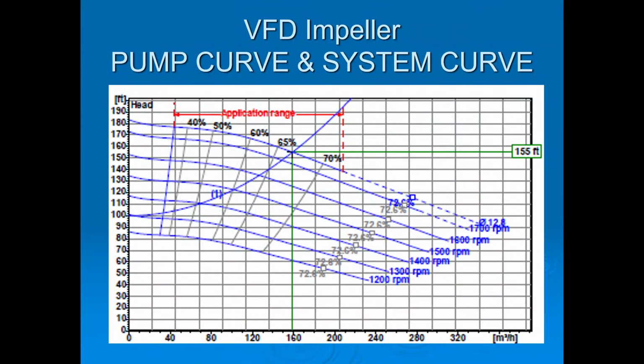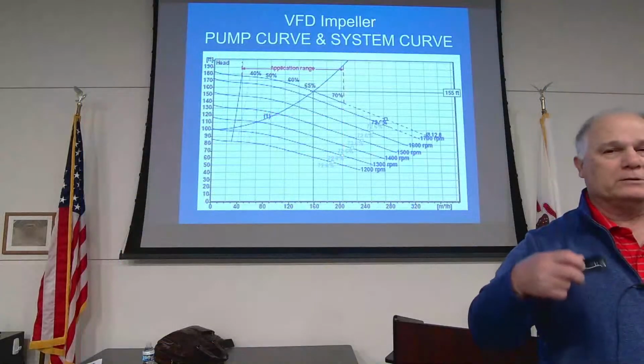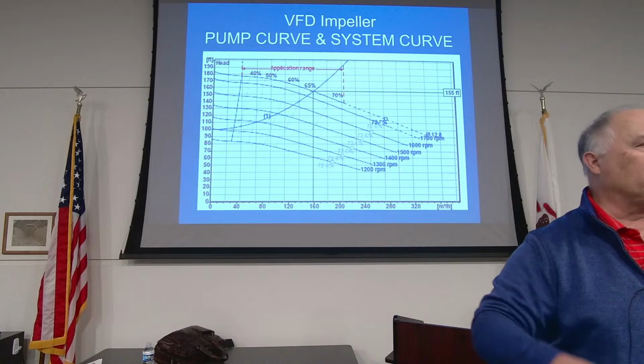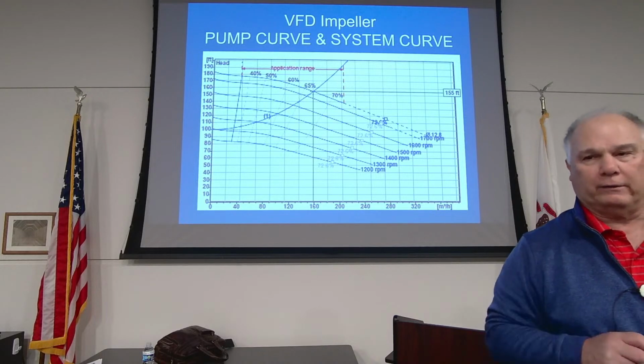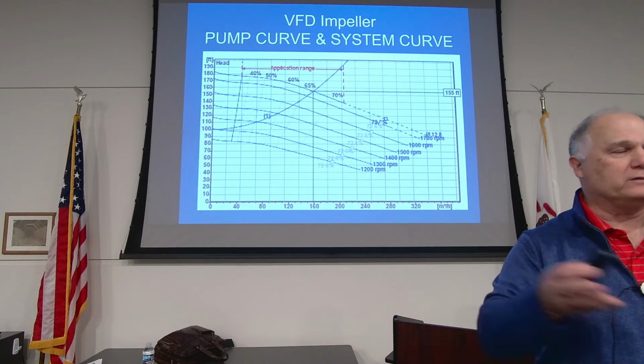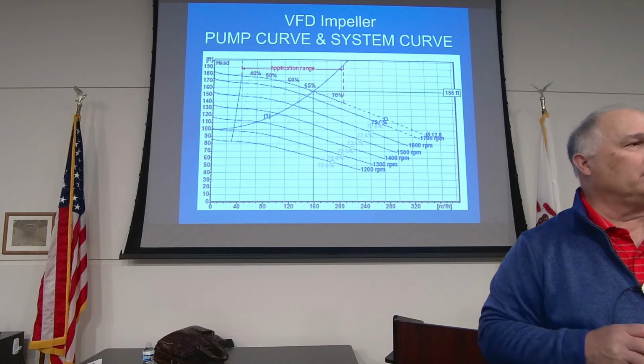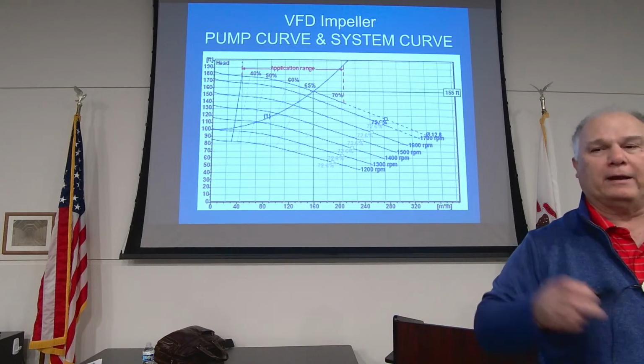VFDs are a great scenario. We love VFDs for the right application. Sometimes VFDs don't make any sense. They're just a sophisticated soft start. It just depends. You gotta look at the system, you gotta look at the design profile, what you have, but anything greater than 20 horsepower is gonna either have a soft start on it or a VFD on it from that perspective. But you can control the exact amount of flow you want based on that system curve and RPM of that pump.